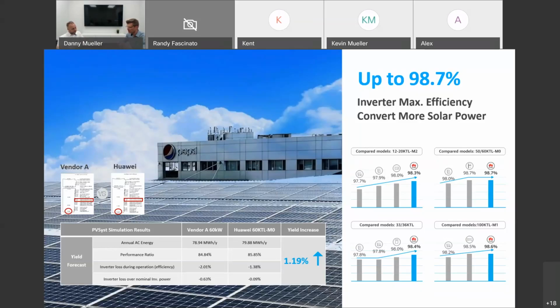And that's the pure magic where today high efficiency is not really a sales tool anymore, or that you make a lot more production versus a much lower efficiency unit. It's all about enabling the secondary features that you have a compact, high density unit, so the power to weight and the power to volume ratio, and enabling just an effective cooling method for a wide input voltage range without having to deploy forced air cooling methods, that you don't have fans in the system, which might fail over a certain time and you have to replace them and things like that.